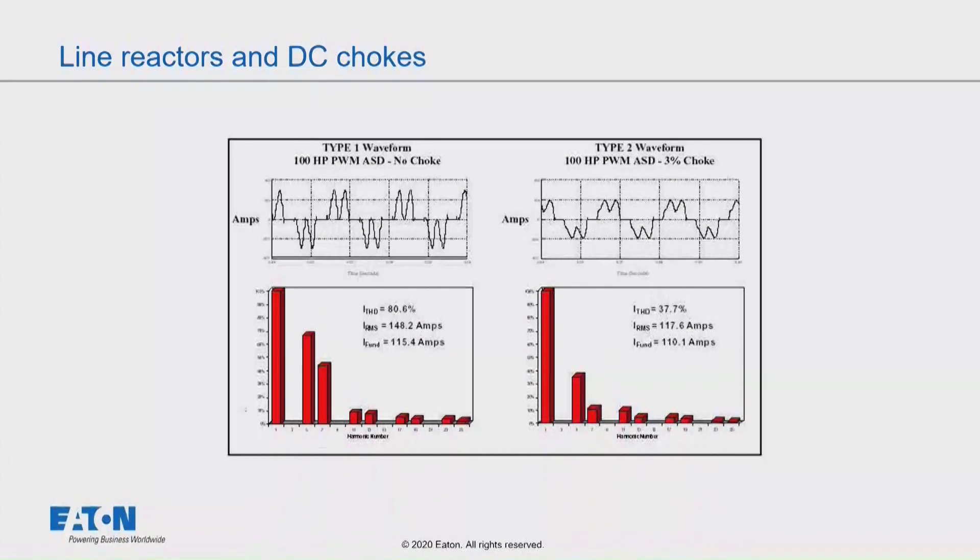Now if we take a look at this graphic, this graphic shows about 80% distortion for a drive that has no line reactor in front of it. In fact, every drive has about a half a percent built into it inherently in the conductors. But if we purposely put a 3% reactor or choke, we get a reduction of about half. We get down to about 40% distortion.